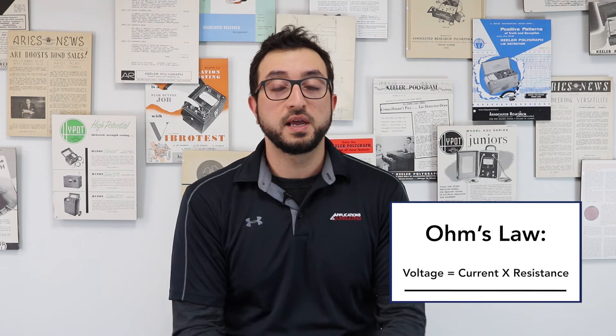This resistance is displayed as a quantifiable value, usually in the range of mega ohms. The IR test is not a very commonly required test per the test standards, due to it being very similar in nature to the high-pot test. The most common applications of IR tests are for repaired equipment or the motor industry, where the windings and the insulation of the motor windings are tested using the IR test.